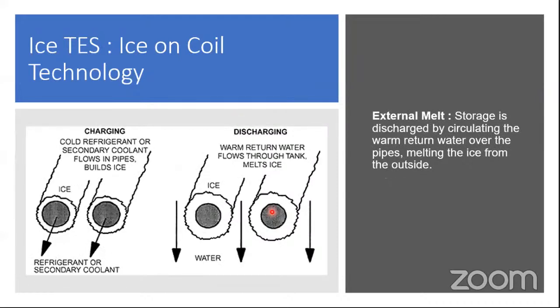Very similar to this is another classification of ice on coil technology, that is external melt. The ice formation happens the same way as explained previously. However, in the external melt, the chill water is made to pass over the ice formed, and that is how the cooling is extracted. So that is external melt, ice on coil technology.